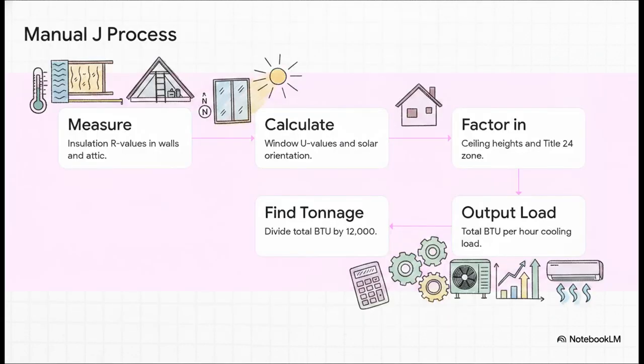So what does this look like in practice? An honest HVAC pro will spend about an hour at your house meticulously evaluating it. They'll climb into your hot attic to measure insulation R-values, calculate U-values on your windows, and check which way those windows face the sun. They factor in ceiling heights, your specific San Diego microclimate, the whole picture. Only after crunching all that math will they output the exact BTUs per hour your home demands. It leaves zero room for guesswork.